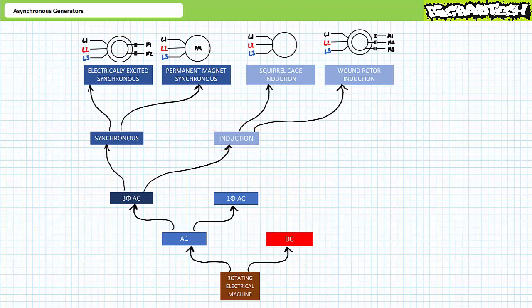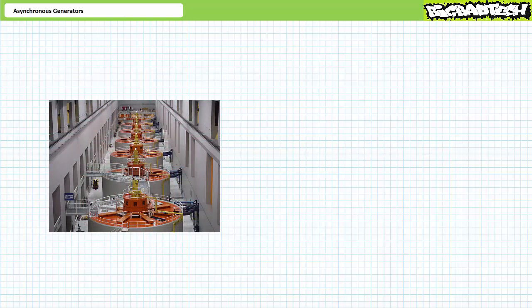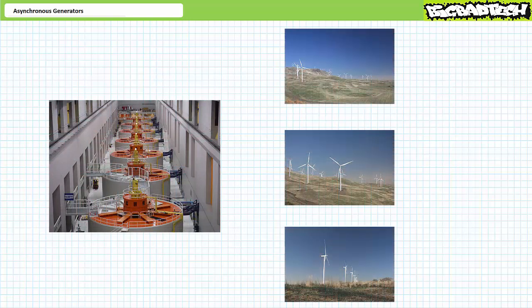The power an asynchronous generator necessarily draws for operation is directed towards a reactive interchange and goes towards establishing the rotating magnetic field in the stator. This implies asynchronous generators must continually consume reactive power even when exporting real electrical power for use. Synchronous generators, in contrast, can operate at unity power factor given proper control mechanisms. Because of this important distinction, you'll often find synchronous and asynchronous generators working together — some large, expensive, complicated synchronous generator establishes the grid, and then numerous smaller, inexpensive, comparatively simpler asynchronous generators use this established grid connection to come online and share the load.